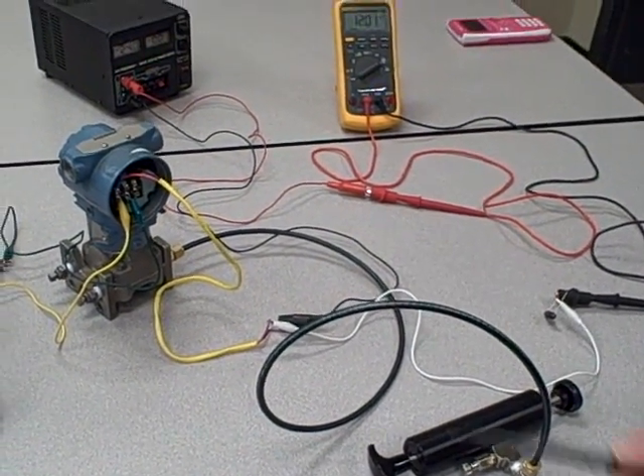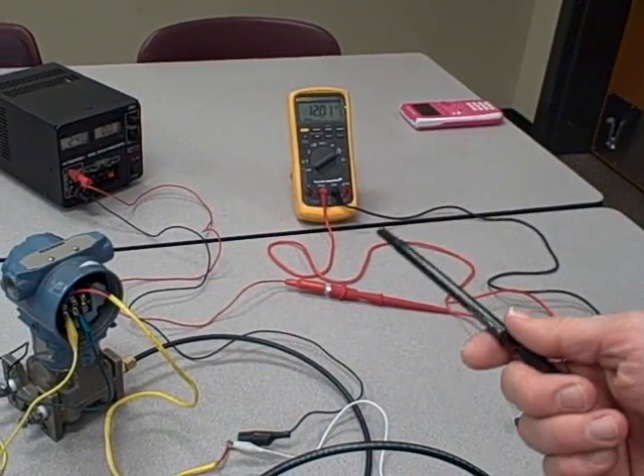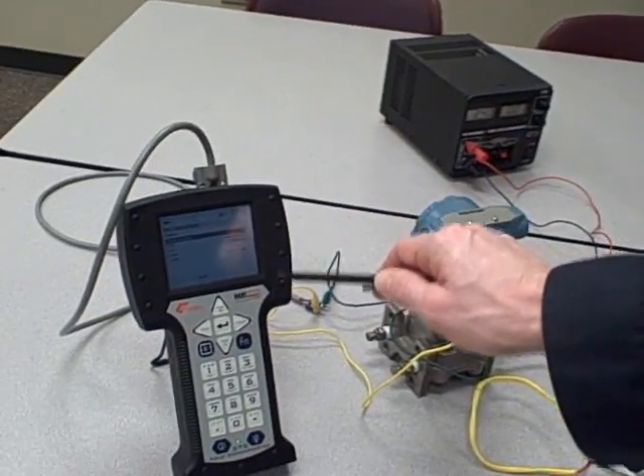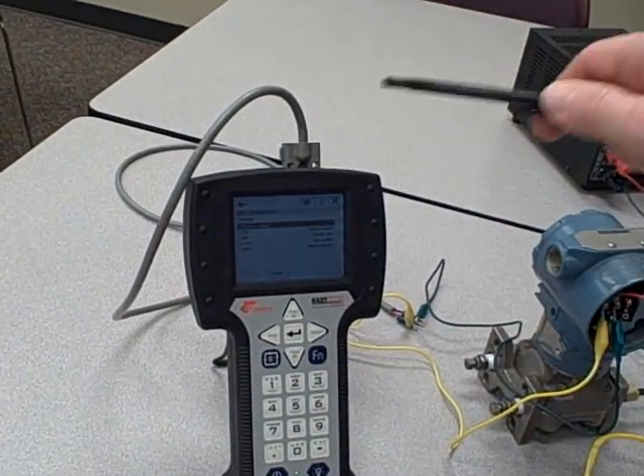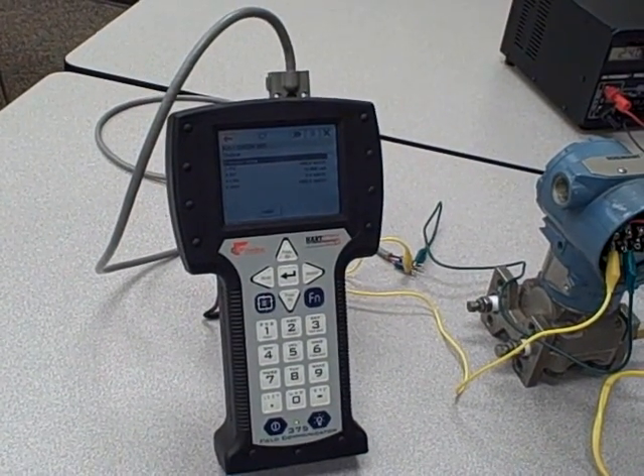So I pressured it up to about half scale, 50%, 12 milliamps, and what we're doing here in addition to looking at the current, we're also monitoring what the transmitter is seeing through this HART communicator. This is an Emerson Model 375 field communicator for HART and for Fieldbus.